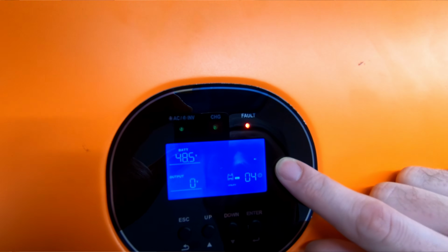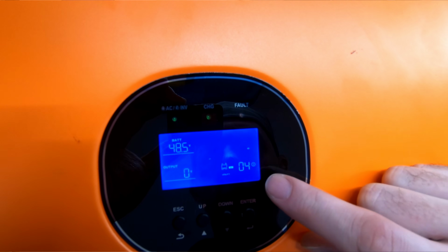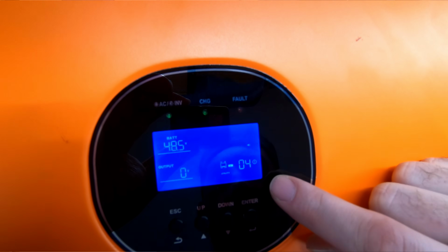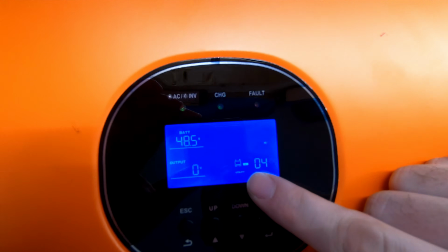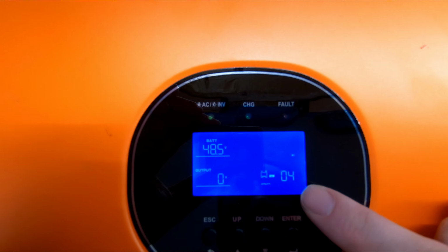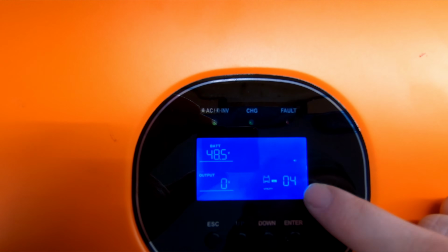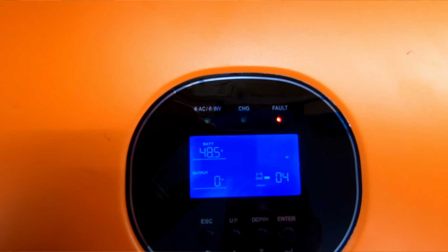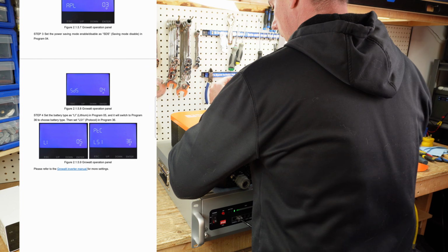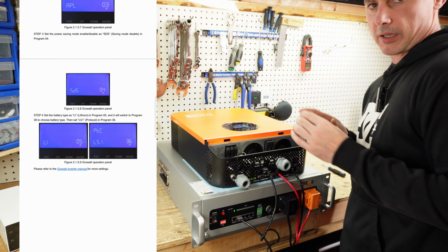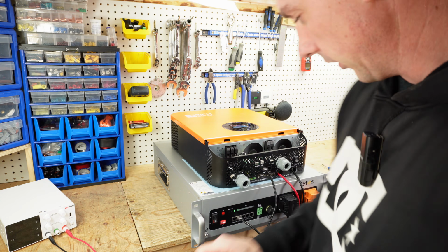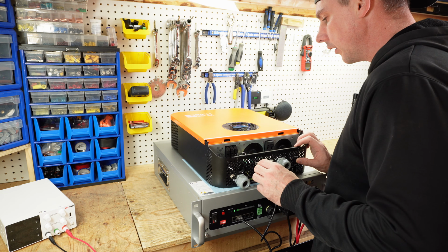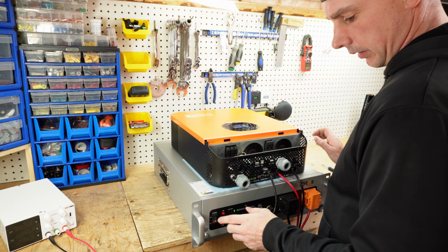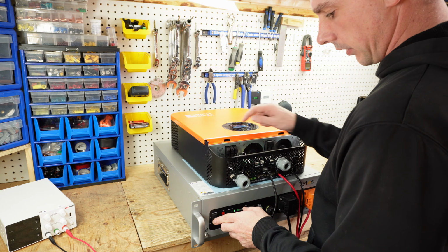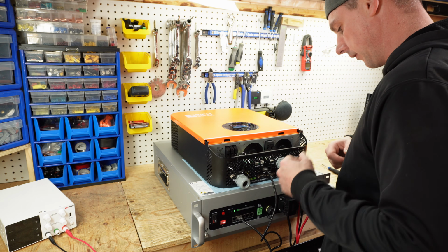Okay, now I'm getting a fault of 04. I think that's because this battery is low. You can see we are in LI utility, but we have a fault of 04, but I think that's just because we have a low battery from the discharge test we just performed. So I'm going to turn this off, and then I'm going to hook up utility power to this.